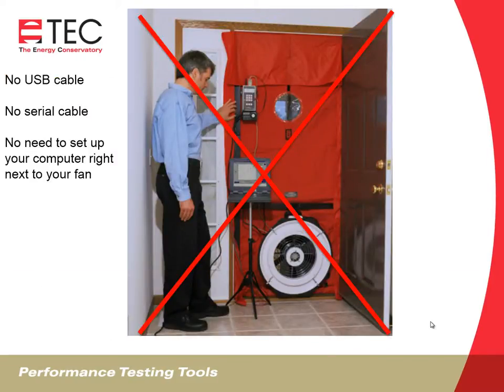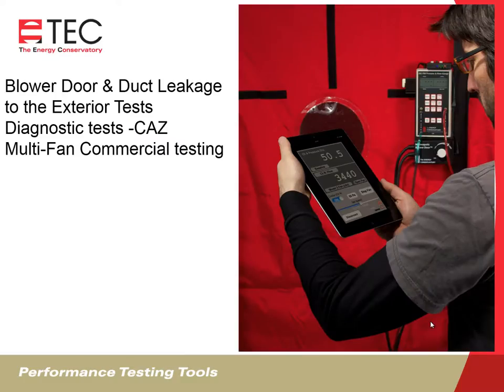With the Wi-Fi Link, you're not going to need a USB cable, you won't need the old school serial cables, and you're not going to need to worry about how close you have to set your laptop to your blower door fan. You'll be able to do blower door tests, duct leakage to the exterior tests, control your blower door fan, and diagnostic testing. You can do a CAZ test where your iPhone or iPad becomes a virtual DG700, allowing you to see the pressure change in the CAZ as you walk through the building creating events. Every time you turn on an exhaust fan or open or close an interior door, you're going to see the change in pressure in your CAZ.